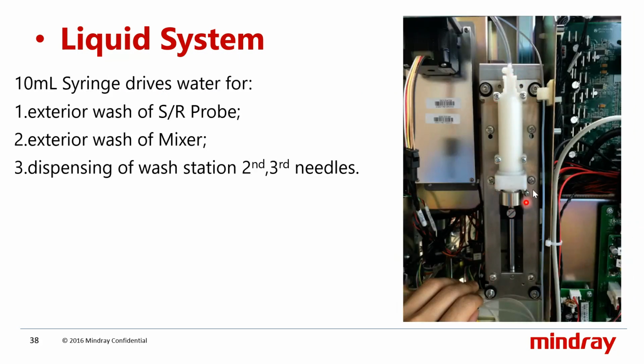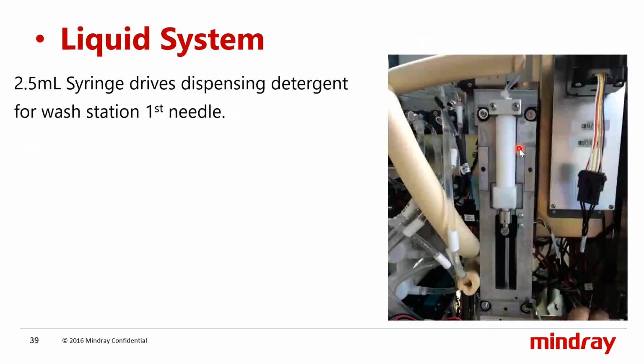and coming to this syringe, we discussed syringe 01. This is going to dispense the water through the wash station and wash wells, sample and mixer wash wells. So this is a 10 ml syringe, used for sample probe external wash, mixer external wash, and dispensing of the wash station second and third needles. Okay, and it is driven by a motor. And another syringe is a 2.5 ml syringe, which is dispensing the detergent in the dispensing probe 1 wash station first needle.